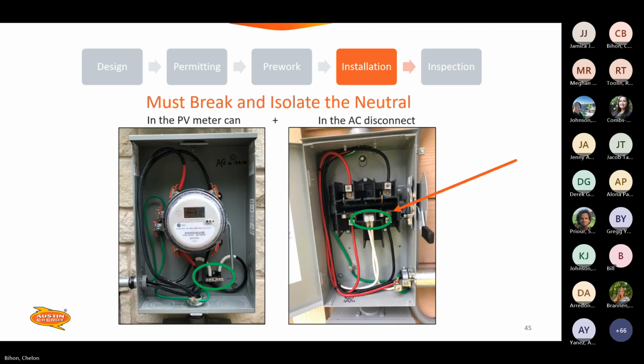Must break and isolate the neutral. Cut it, put it in a Polaris block or similar isolation bar, you can see there inside that meter can. Must be a full-size neutral. Going to the disconnect.